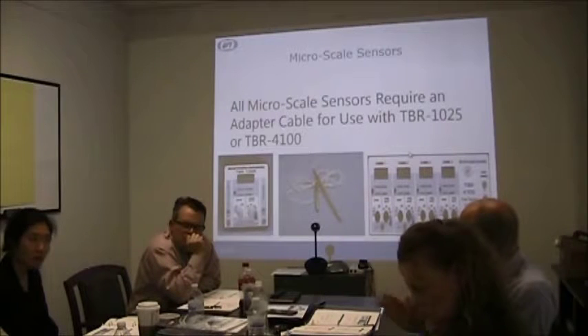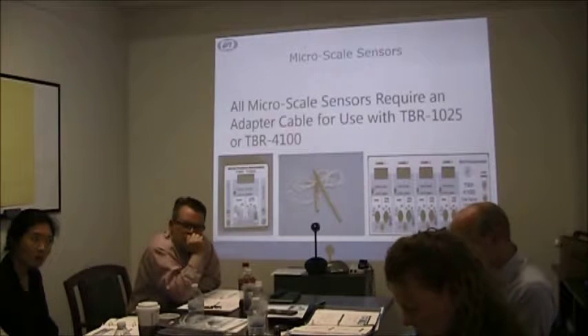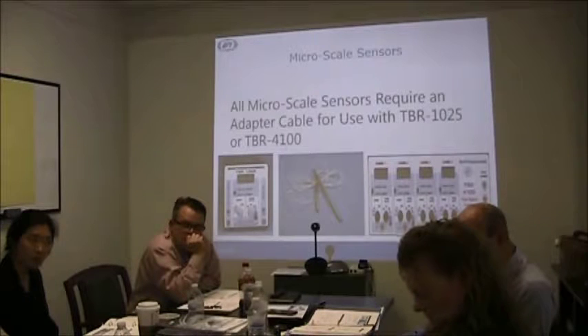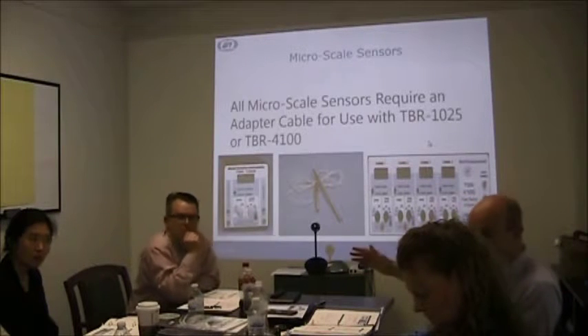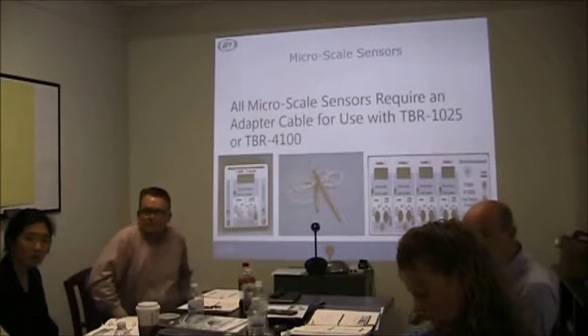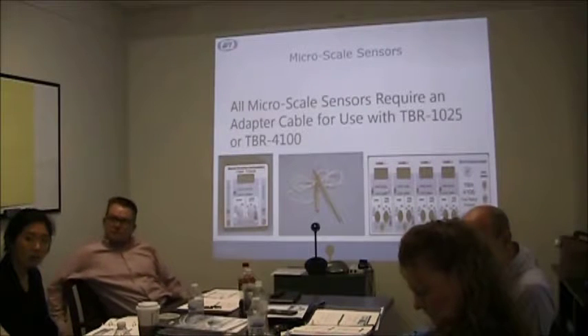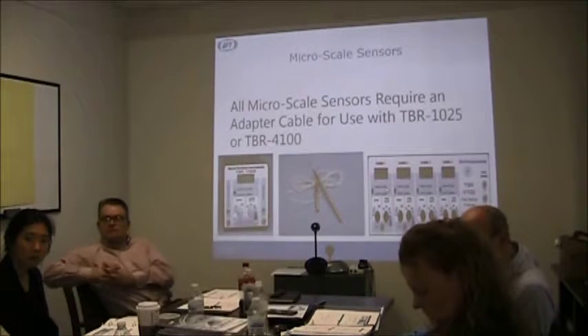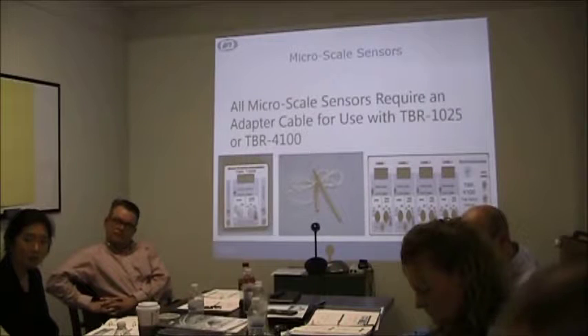And if you have, for instance, hydrogen peroxide at 200 micromolar, how will that impact it, because it's only 200 micromolar? If you have 200 micromolar, can it still be accurate? Well, it depends on the sensor. For nitric oxide, the 2 millimeter sensor is designed to measure optimally at 80 micromolar and higher.